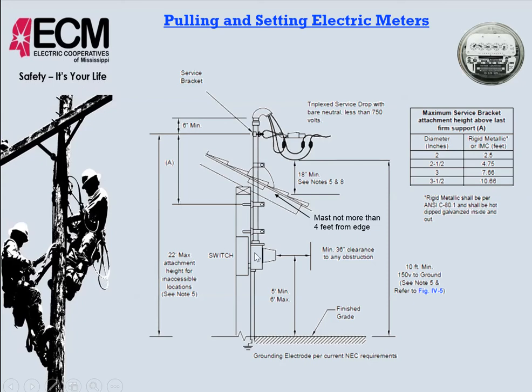So you have your meter base screwed or bolted to the wall, however it is attached. The meter itself needs to be at 5 feet minimum and 6 feet maximum. So 5.5 feet would hit right in the middle of that. So 5 feet minimum, it has to be at least 5 feet and can't be more than 6 feet above the ground. And then where this is attached and secured and strapped to the wall or wherever has a distance here of A.